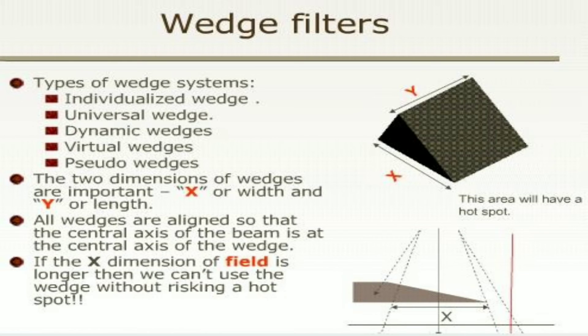Types of wedge systems are individualized wedge, universal wedge, dynamic wedge, virtual wedge, and pseudo wedge. The two dimensions of the wedge are important: x is the width and y is the length. All wedges are aligned so that the central axis of the beam is at the central axis of the wedge. If the x dimension — width of the field — is longer, we can't use the wedge without risking a hotspot.